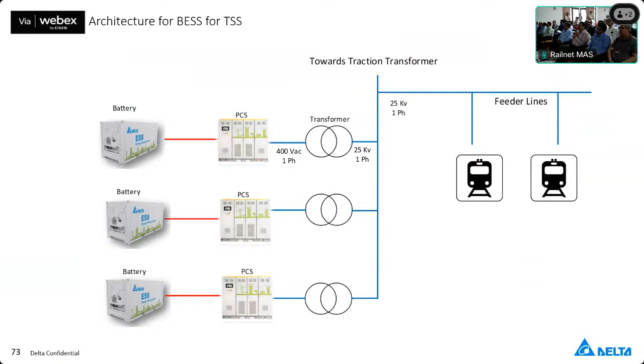Based on this, we did an analysis and came up with an idea wherein we can go with a 6 megawatt, 3 megawatt hour battery storage system with a single phase converter, which looks something like this - an application where the battery energy storage comes in a container, which is a portable entity. Even the PCS can be put inside a container with a single phase transformer directly to 25 kV, wherein it can cater to the load. This is a simple SLD of the concept.